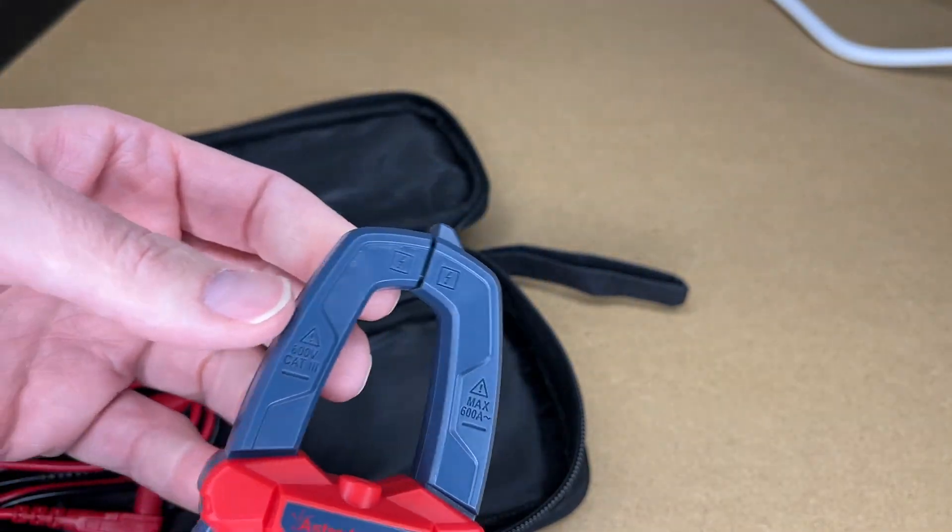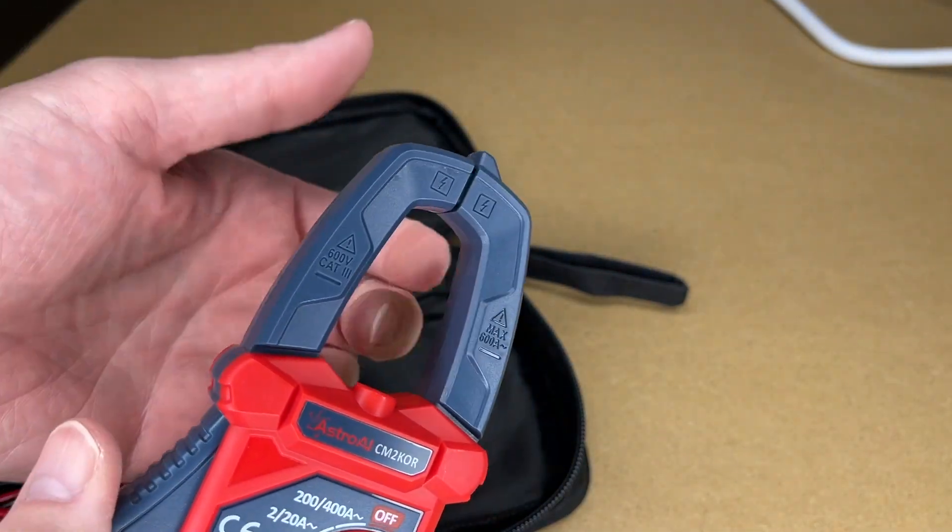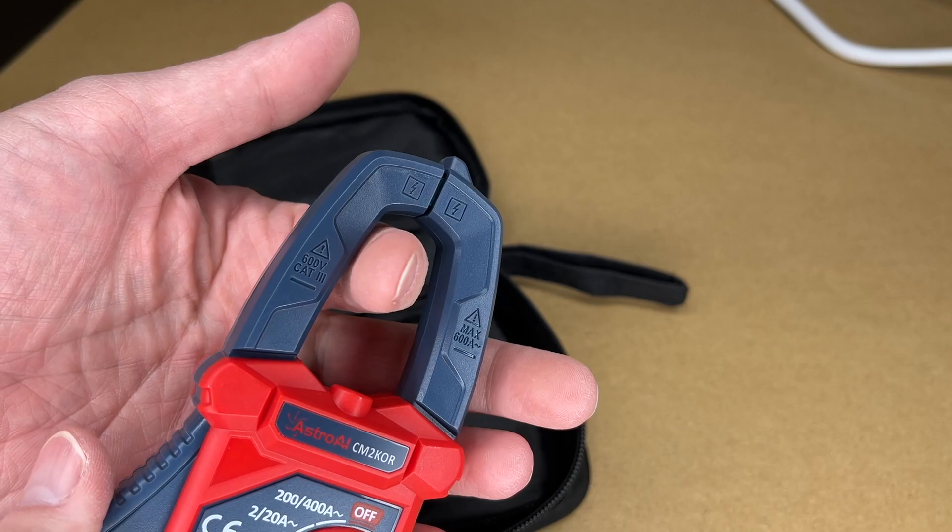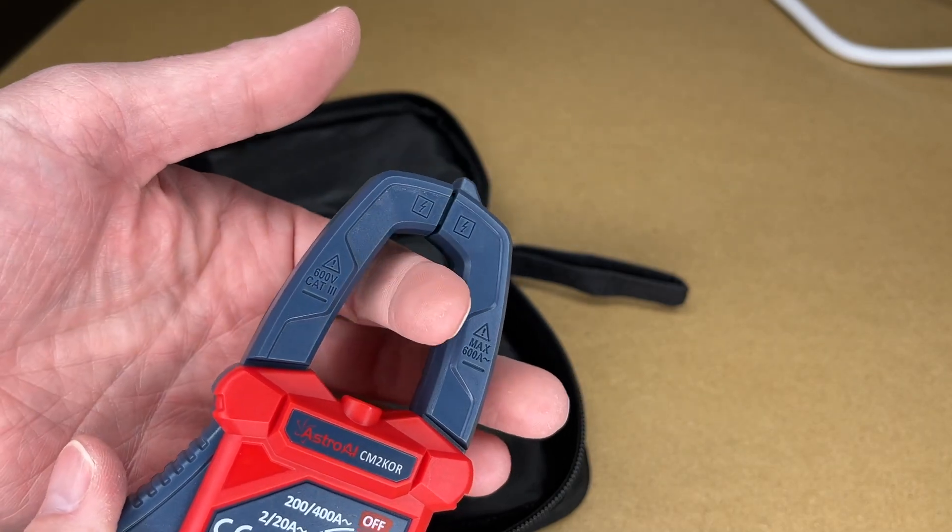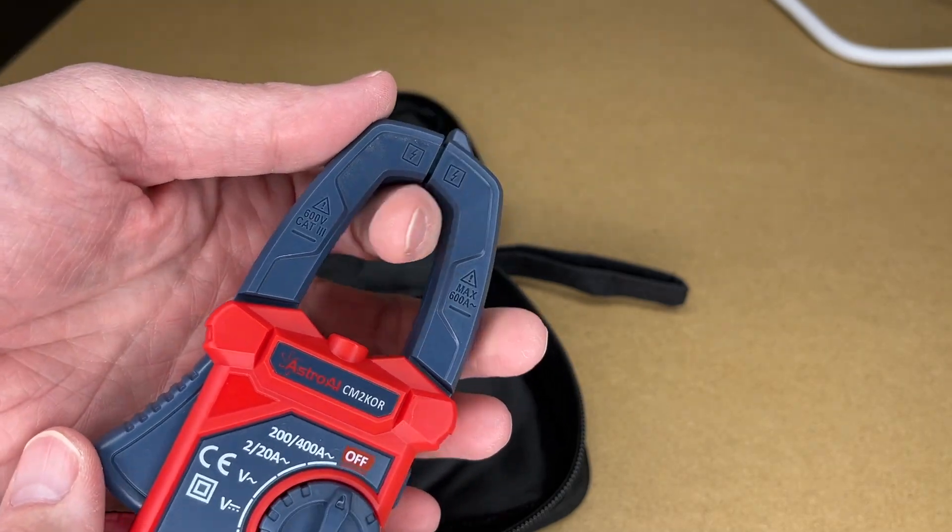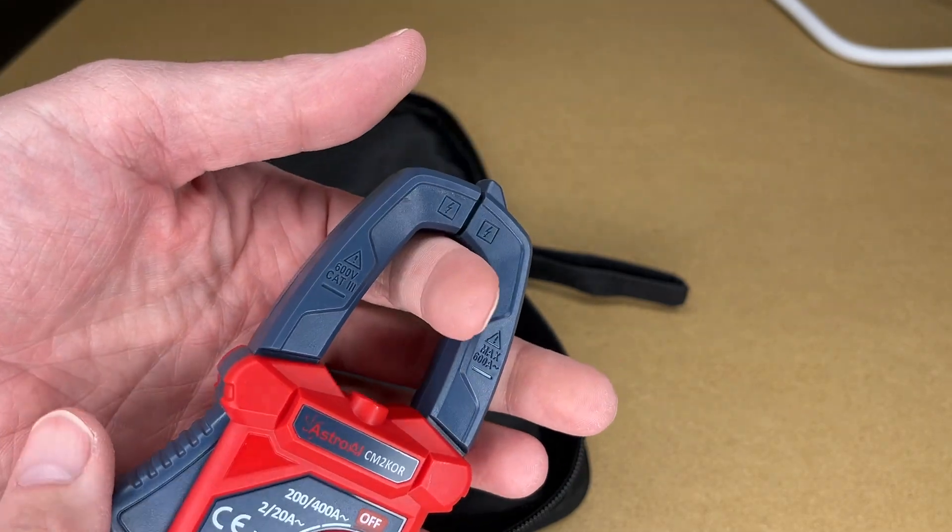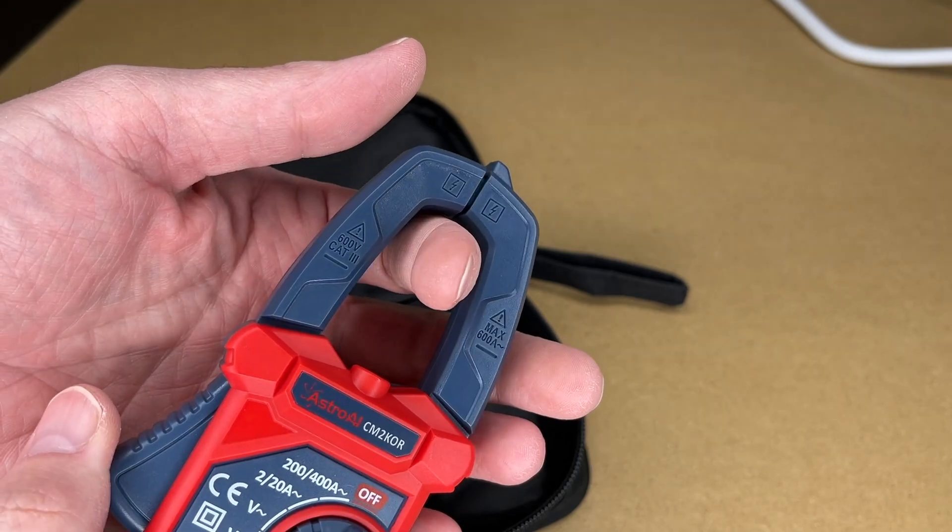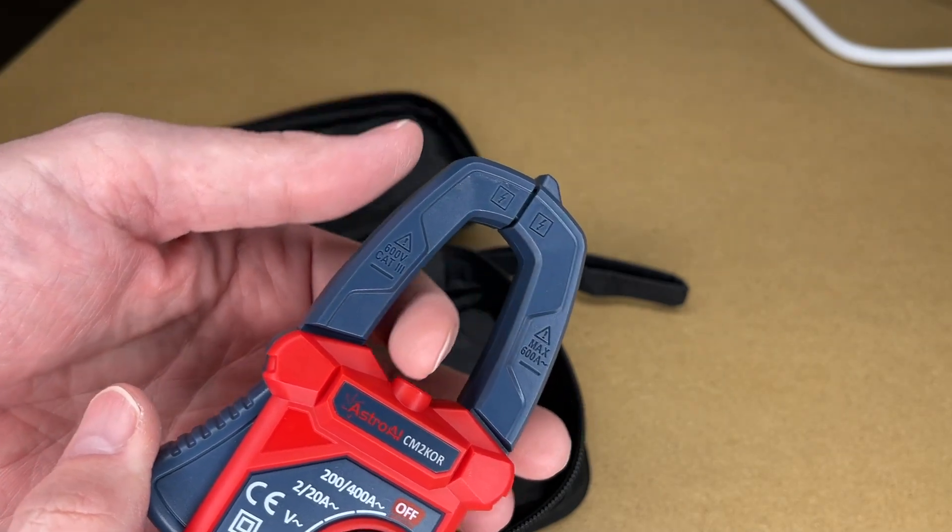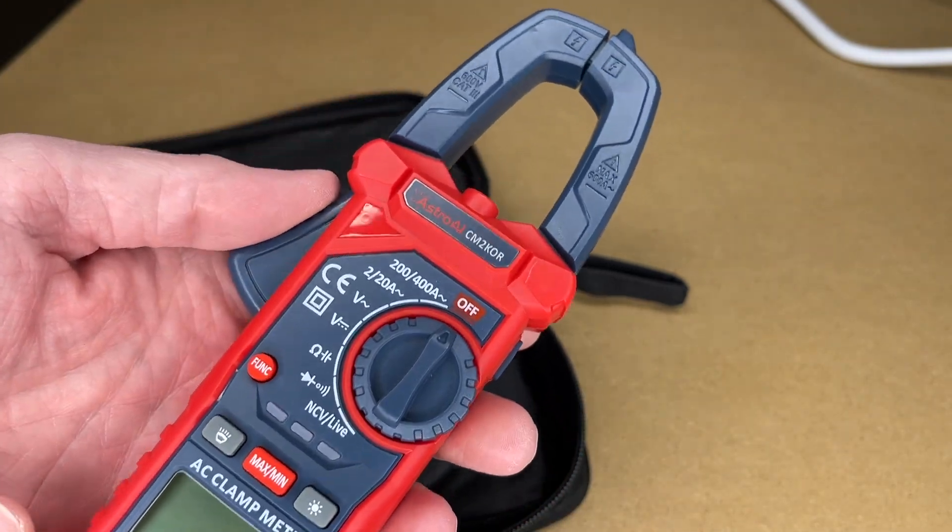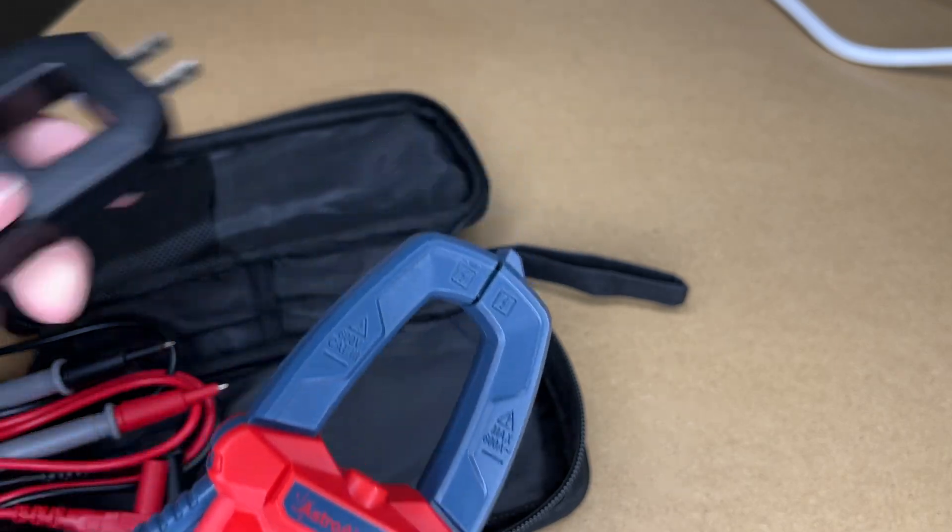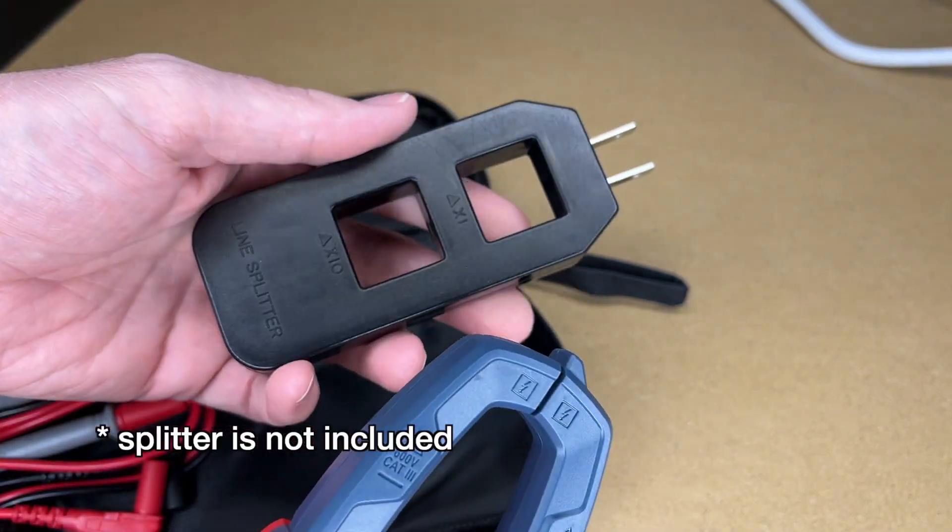So this is for the amp meter. You would place this around a single conductor, so this would be your hot. You would put that around your hot. You can't put it around both because those will cancel each other out. So you put it on one of the conductors and then this will read the amps. So if you have a cord you want to read on, you can use a device like this as a splitter. You plug this in and plug another device into here, and then you can put the amp meter around there to read it.